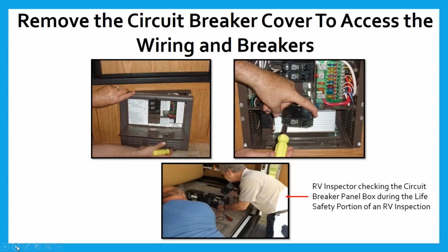And this is what you and I have to do. We need to be getting into these panel boxes, and I'm going to say a minimum of one time a year. And if you've been in a situation where you've been pulling a lot of power—say during the winter when you're using a lot of heaters, or in the summer when you're using a lot of air conditioners—folks, we're only talking about being in there maybe 15 or 20 minutes, but it's amazing what you'll find inside that panel box, and what you'll be able to fix and remedy. And it doesn't cost you anything. You can do this yourself. You don't have to wait on some technician to come out there, you don't have to wait 6 weeks to get into a shop. You can do this yourself.